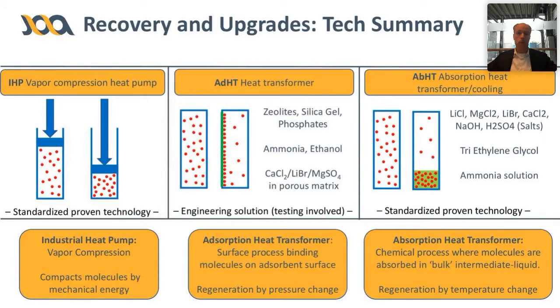So the waste heat of, for example, 80 degrees C, 85 degrees C can be used to generate chilled water of 6 to 12 degrees C. And typically, this is not the first thing to think of in your processes when you're looking into waste heat, because, well, we're talking about heat. But it might be very interesting to explore this opportunity, especially if you are using process cooling.